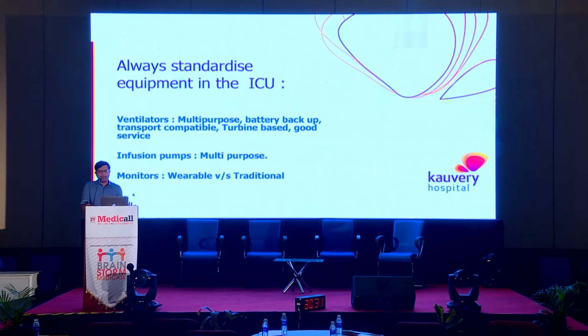It's important to have battery backup. You also know power can fail anytime, so if you don't have good battery backup, it can cause trouble, so don't compromise the battery backup. And also ensure the ventilator that you buy is transport compatible. You don't have to buy the biggest, most expensive all singing and dancing machine. The ventilator that I mentioned can also be used to transport the patient. So if it is going to a different hospital, or going to a CT scan, then this ventilator can combine and do all of these things.